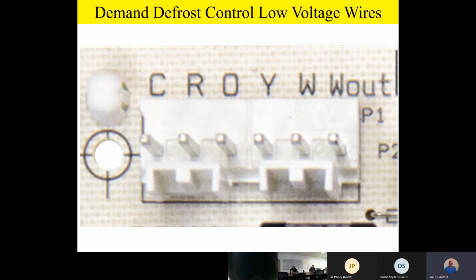So you'll see that we blew that up a little bit to give us a little better look at those pins or those terminals. Now remember, team, I've removed all the harnesses off this board so that we can talk about each one of those pins, inputs and outputs individually. Where these pins are, you'll actually have a harness wired in such a fashion that you'll have wires coming off it. C is our 24-volt common that's going to be powering the board up. That'll be one side of the board being powered up all the time.